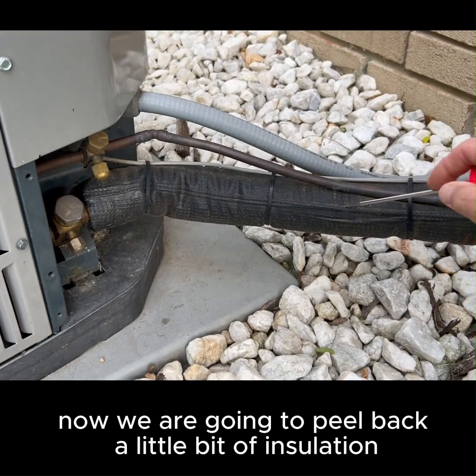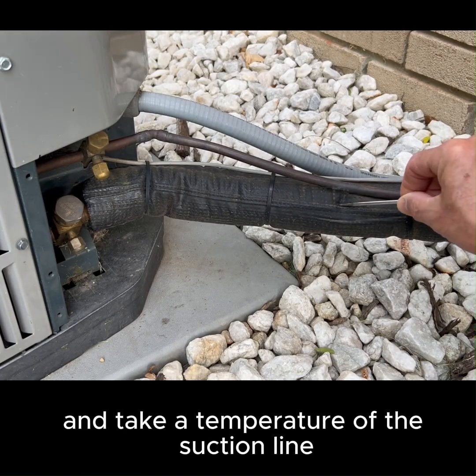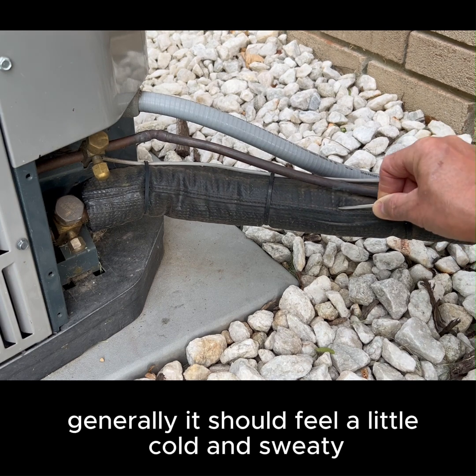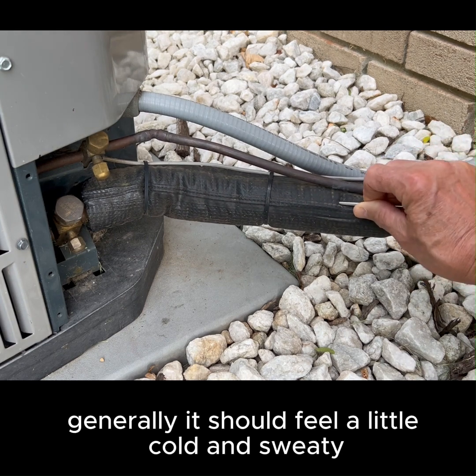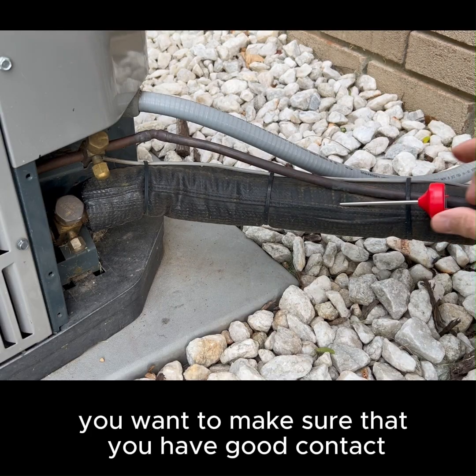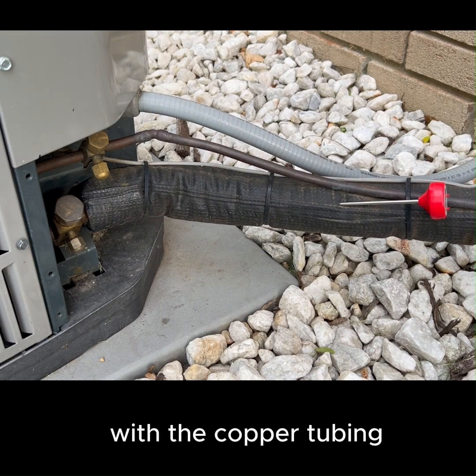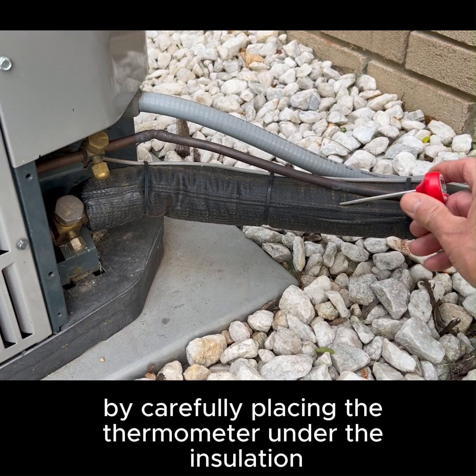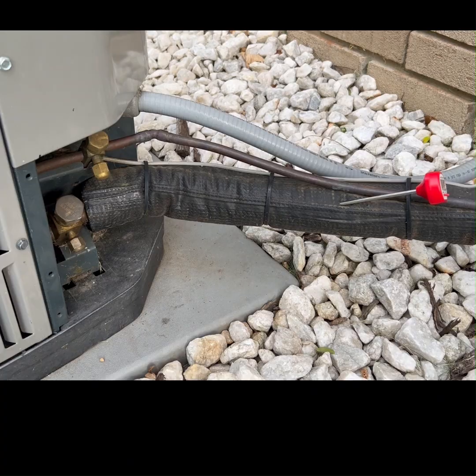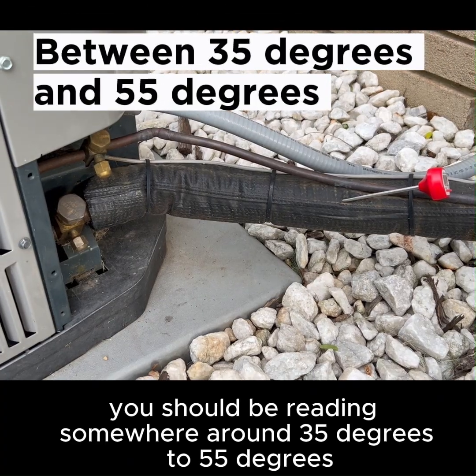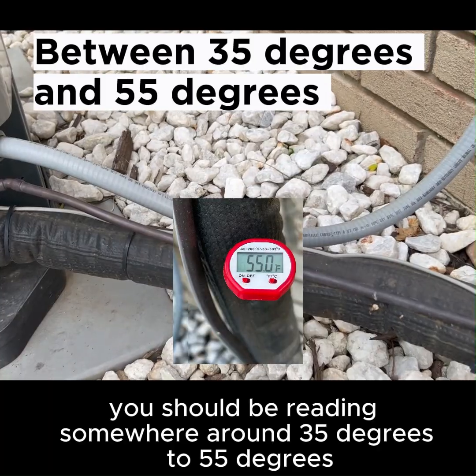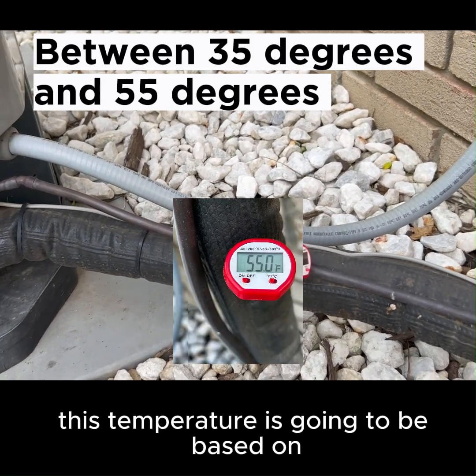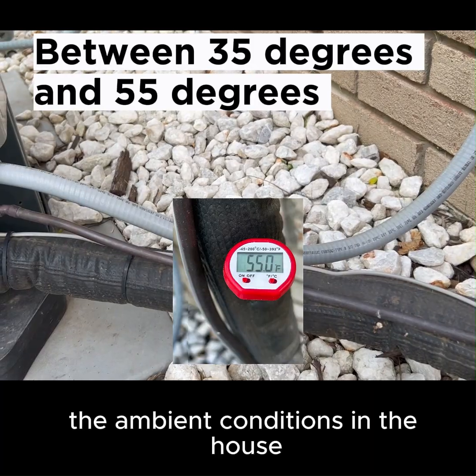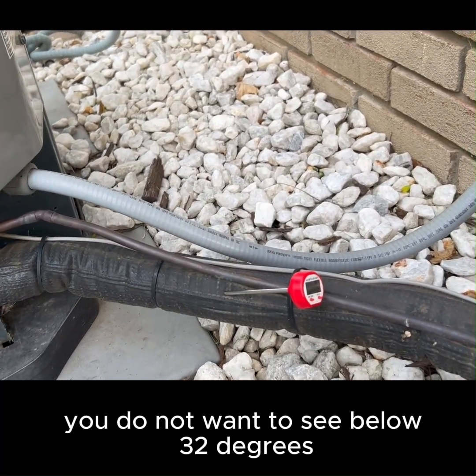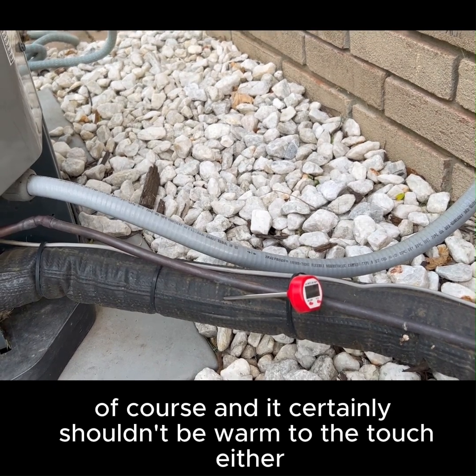Now we are going to peel back a little bit of insulation and take a temperature of the suction line. Generally, it should feel a little cold and sweaty. You want to make sure that you have good contact with the copper tubing by carefully placing the thermometer under the insulation and touching the copper tubing. You should be reading somewhere around 35 degrees to 55 degrees. This temperature is going to be based on the ambient conditions in the house. You do not want to see below 32 degrees, of course, and it certainly shouldn't be warm to the touch either.